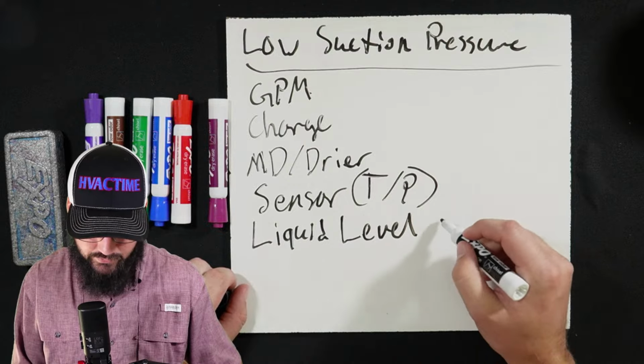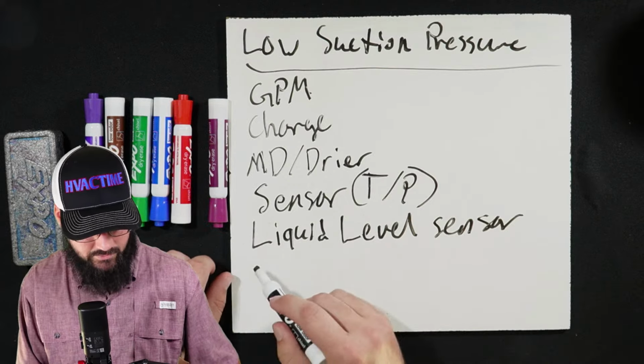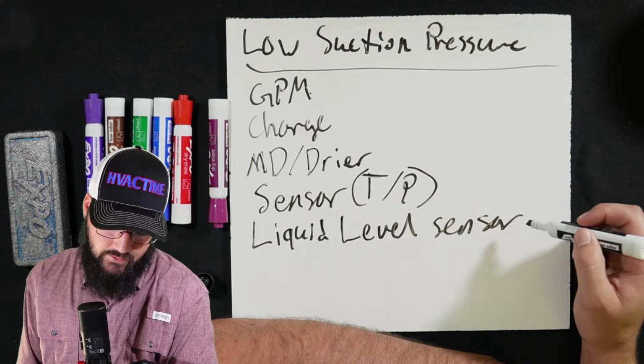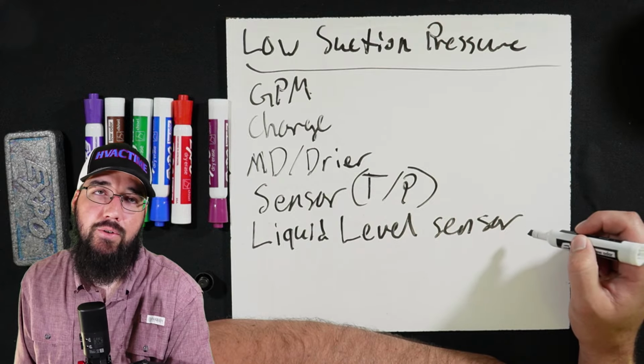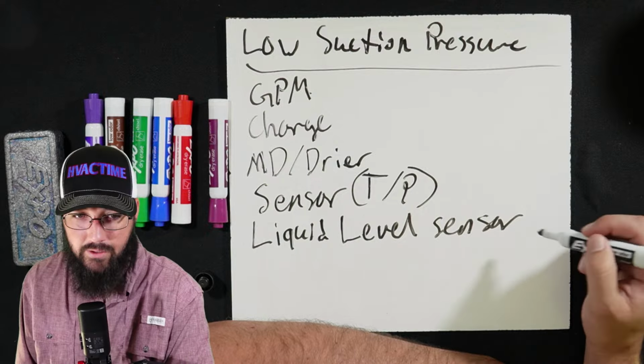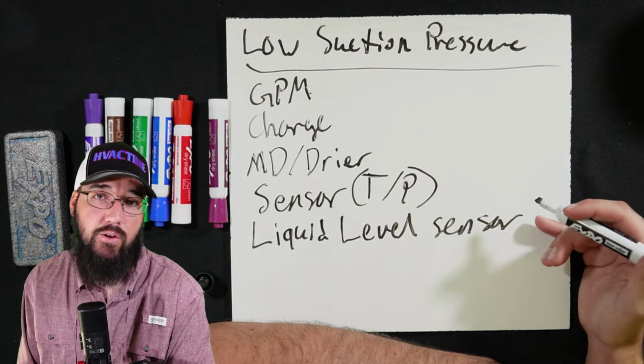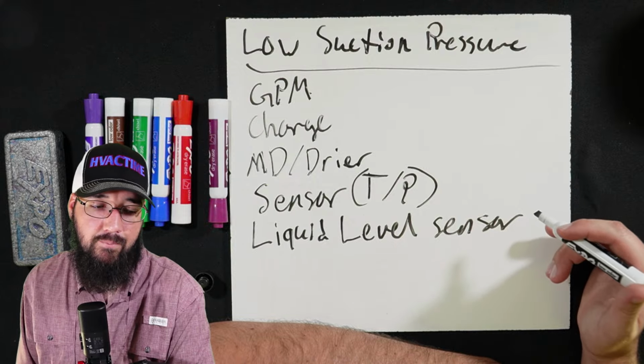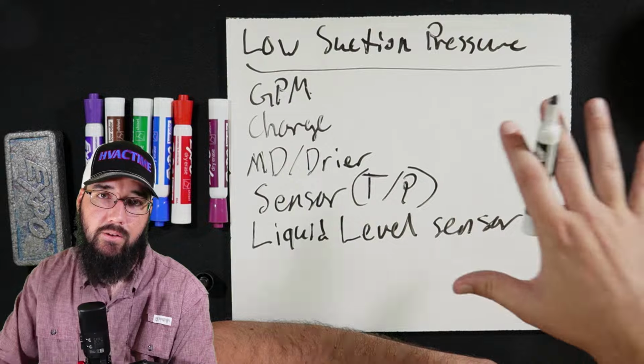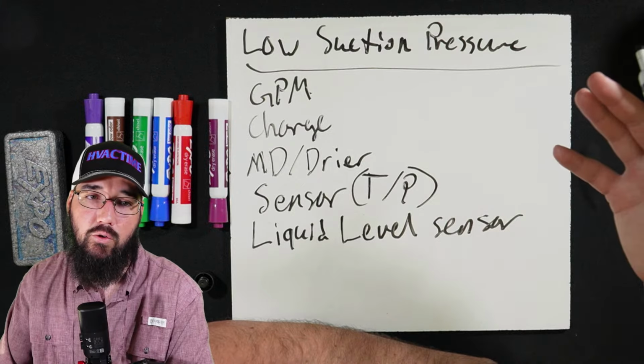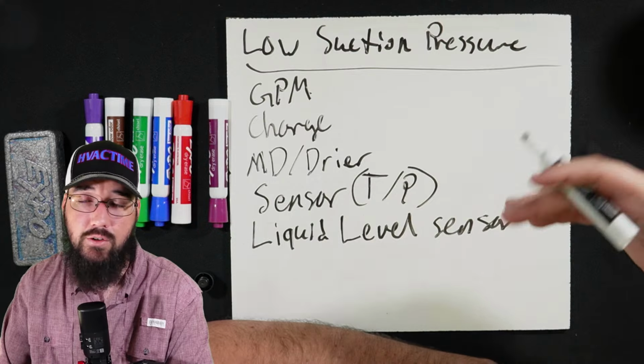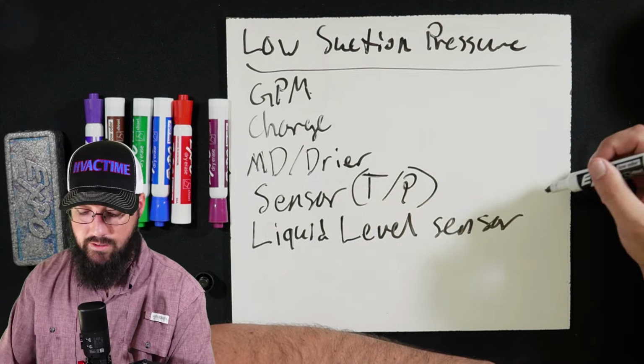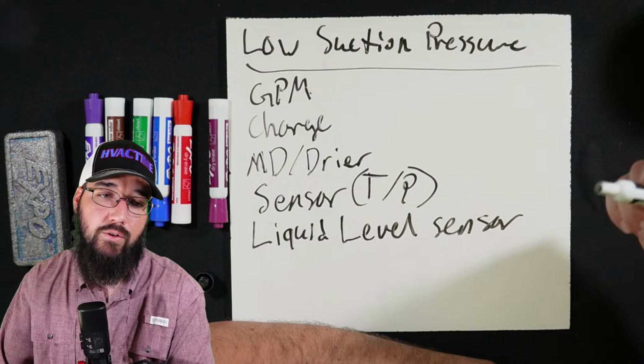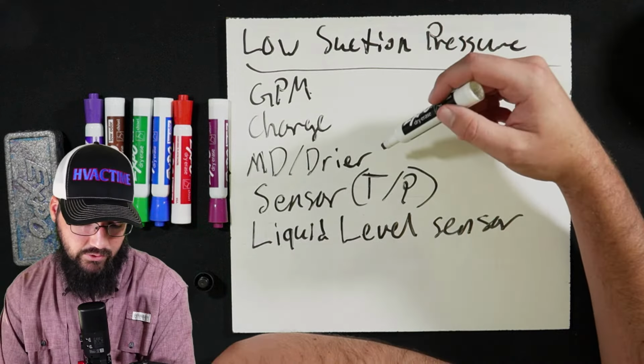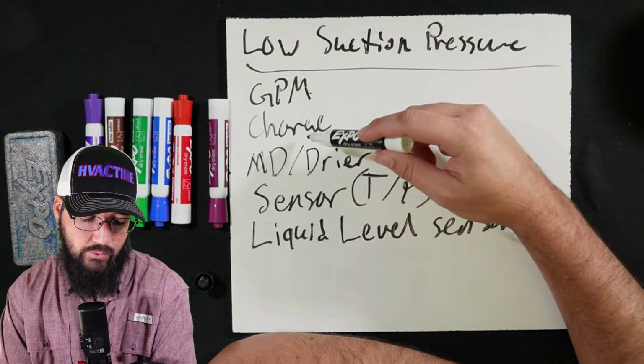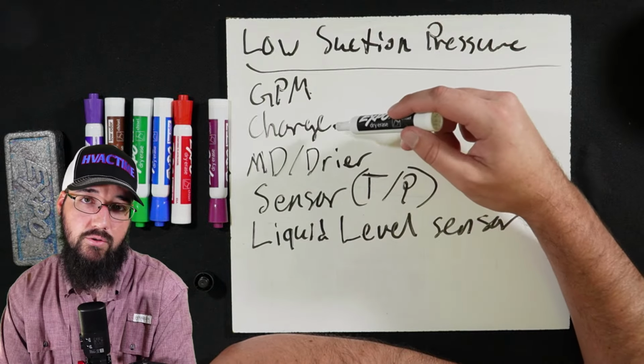Okay. Liquid level sensor. Add the S this time. If this is either out of calibration or just flat bad, right? So we've got a bad liquid level sensor that could be forcing the refrigerant level down and causing a low suction pressure trip, or maybe you're suction limiting. If this level sensor is not reading correctly, it's not going to open the metering device correctly. So this comes back to evaluating whether it's a charge issue or not, right?